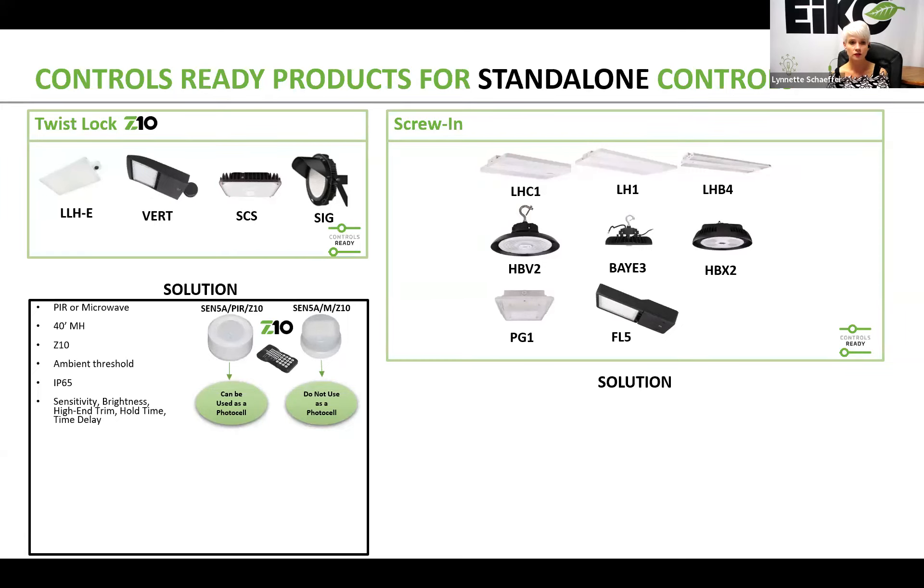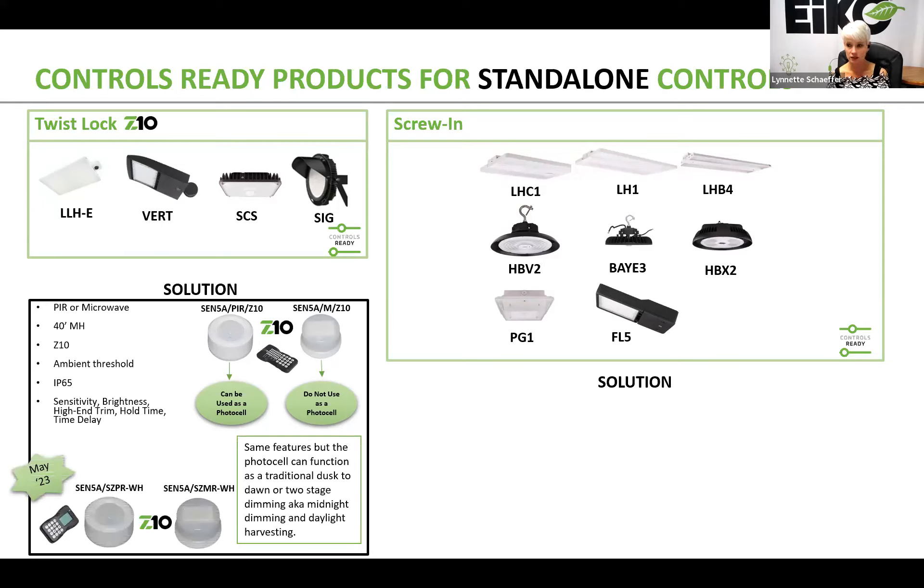You'll see the two previous models of standalone sensors listed here: the SENSA slash PIR slash Z10 and the SENSA slash M slash Z10 — both legacy standalone controls, offered in PIR and microwave, with a 40-foot mounting height, ideally used between 8 and 30 feet. Those featured ambient threshold, IP65 rating, and the ability to set sensitivity, brightness, high-end trim, hold time, and time delay. The two new products replacing these feature the photo cell that can function as traditional dusk-to-dawn, two-stage dimming — aka midnight dimming — and daylight harvesting. That is the biggest improvement.